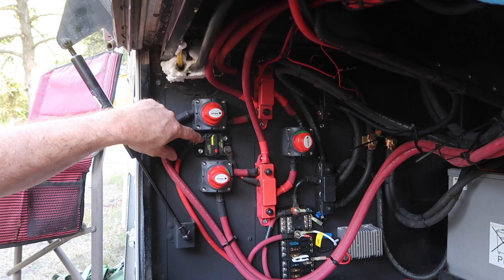The output is on a 25 amp fuse on the 24 volt side, goes to your buck converter and turns it to 13.8 volts, feeding the 12 volt side of the panel. These two big cables were pulled through the frame rails - that was a greasy job. These are a little oversized for what's needed, but that's fine because we had good welding cable available.